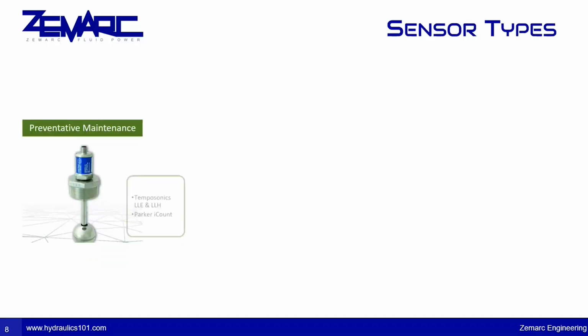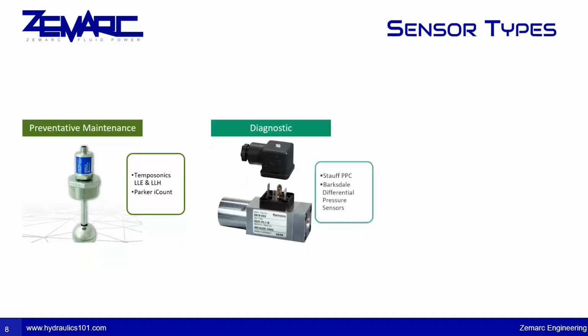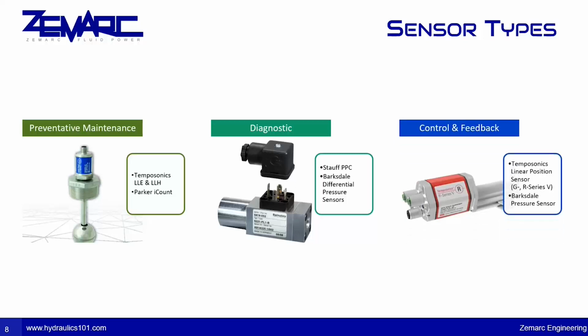So, sensor types. Sensors will fall into one of three main categories: preventative maintenance sensors, diagnostic sensors, and control and feedback sensors. Each type of sensor is designed to detect a specific type of physical parameter and convert it into an electrical signal that can be processed by an electronic device, such as a PLC. So, common ways to conduct preventative maintenance include the regular checking of fluid level in the reservoir and the level of contamination in the fluid.